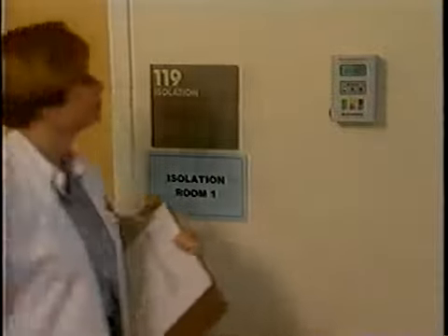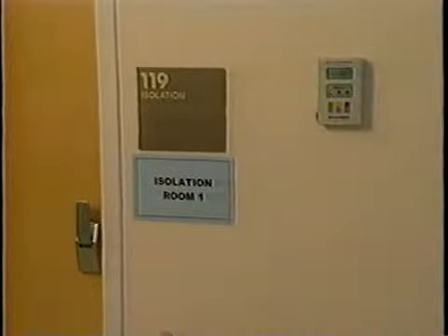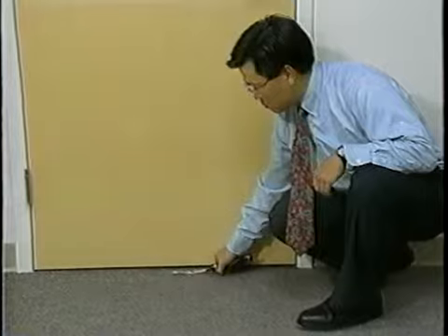The reason for the time delay is to allow staff time to go in and out of the room without the alarm sounding every time. If you have a permanent room monitor installed, you don't need to check negative pressure daily with the telltale, but someone should read and record the monitor pressure reading daily when the room is in use for a TB patient. Also, you should verify negative pressure with a telltale and test the monitor monthly.